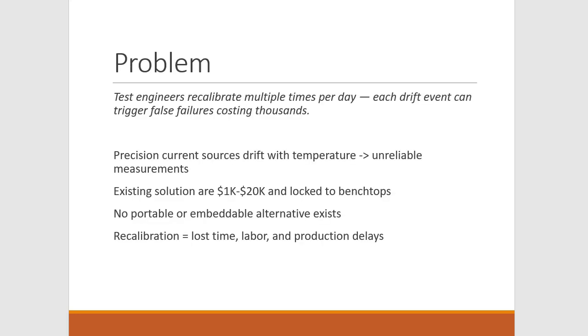The problem our customers, the test engineers, face is that they recalibrate multiple times per day. Each drift event can trigger false failures, costing a certain amount of dollars, and that drift causes unreliable measurements. We're aiming for 0% current drift, and so far we've achieved 0.5% current drift for a 0.25 milliamp source.